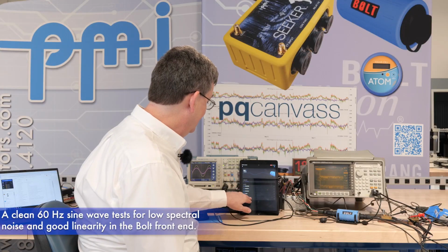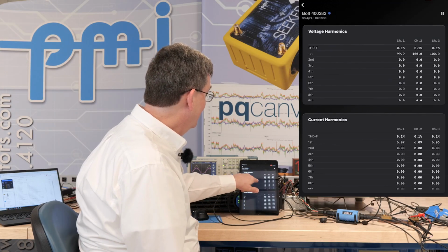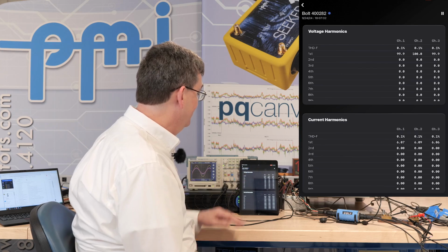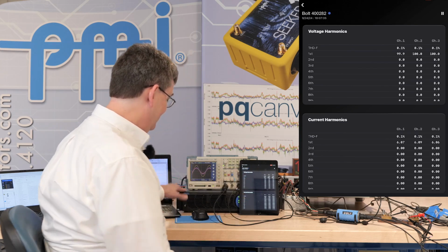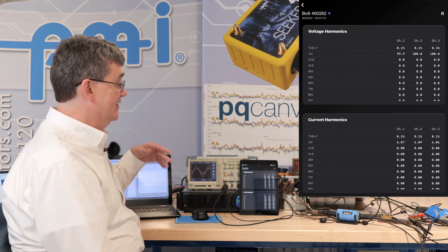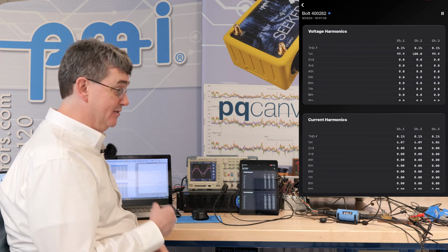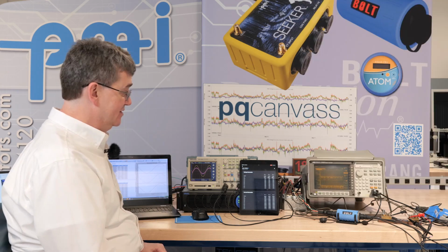Let's take a look at the harmonic meter readings. We can see we're at 0.1% distortion for voltage and for current. That's really the limit of the power supply. That's a very low distortion, very difficult to get below that with a large power supply.